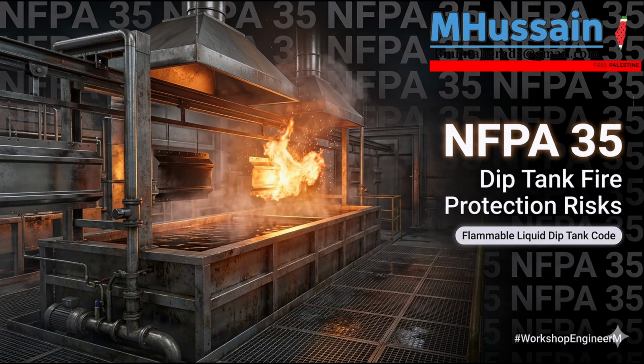Yes. And this is where mechanical contractors must be absolutely meticulous. Let's get into it. Transferring Class 1, 2, and 3 liquids from the bulk storage tanks to the process areas must be accomplished through closed piping systems. You can use gravity flow, or you can use mechanical pumps. But both introduce massive risks if a pipe bursts. Let's start with gravity flow. If you have a massive storage tank on the second floor feeding solvent down to a mixing tank on the first floor, gravity is providing the motive force.